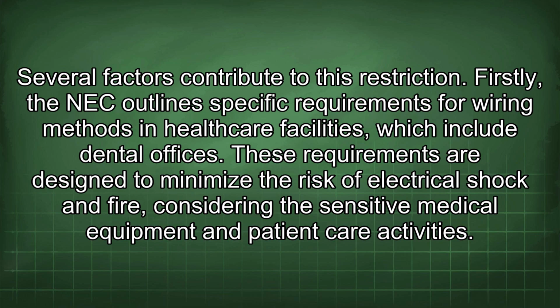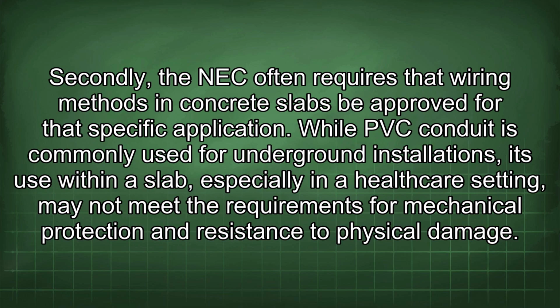Firstly, the NEC outlines specific requirements for wiring methods in healthcare facilities, which include dental offices. These requirements are designed to minimize the risk of electrical shock and fire, considering the sensitive medical equipment and patient care activities. Secondly, the NEC often requires that wiring methods in concrete slabs be approved for that specific application. While PVC conduit is commonly used for underground installations, its use within a slab, especially in a healthcare setting, may not meet the requirements for mechanical protection and resistance to physical damage.